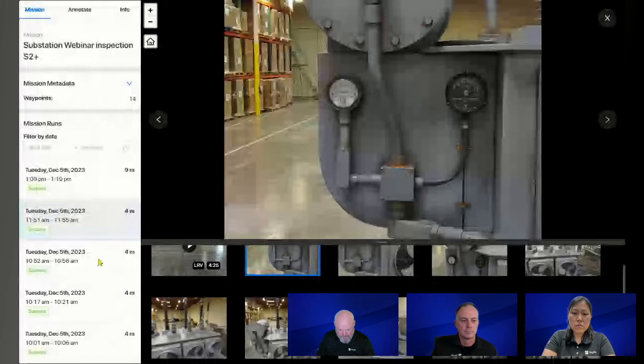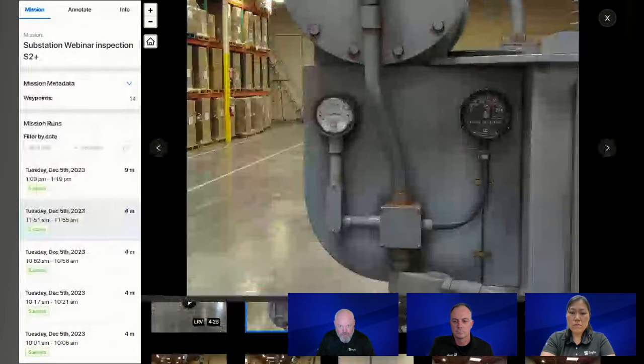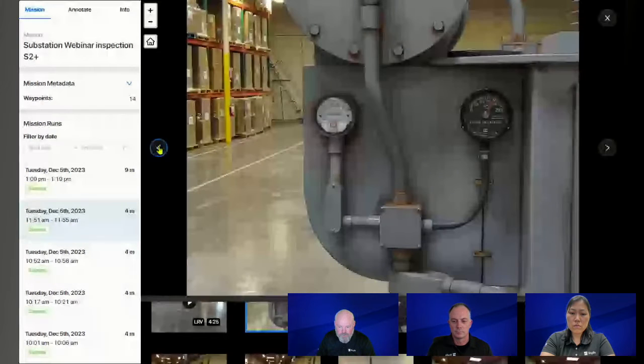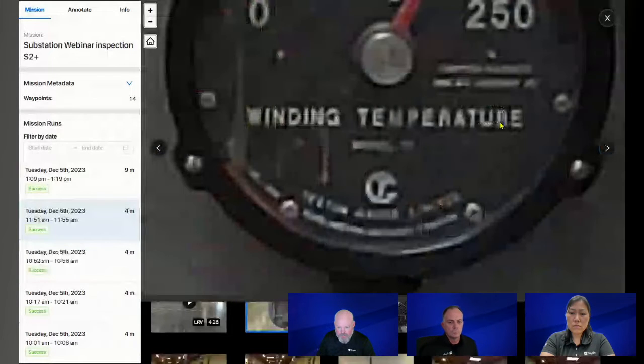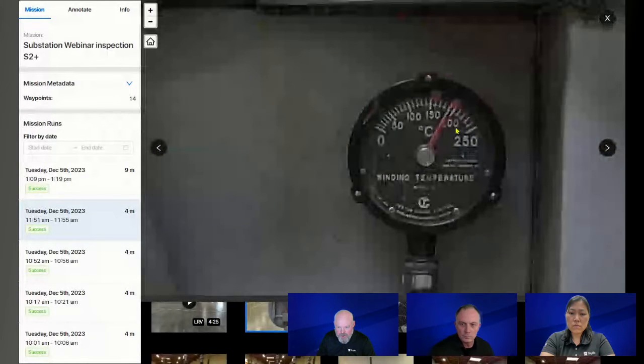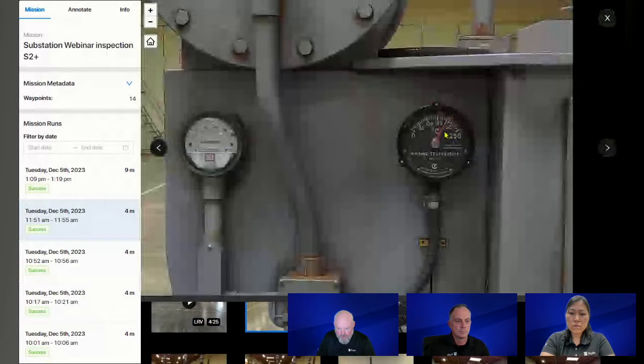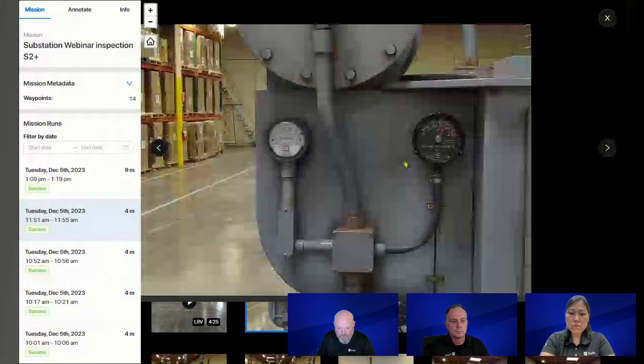So this is an image of that transformer. This was the last photo taken in the inspection, so it goes backwards. What we see here is the windings temperature actually moving more towards 200, and it's contacting the contactors, which should engage the fan relays.